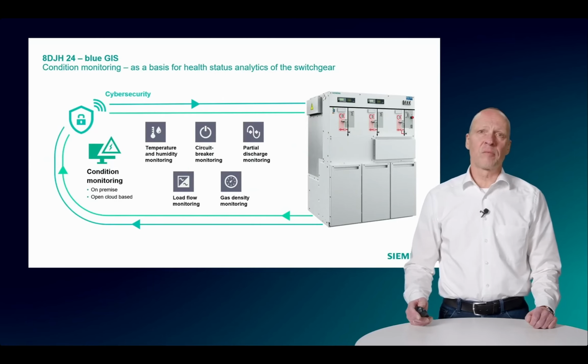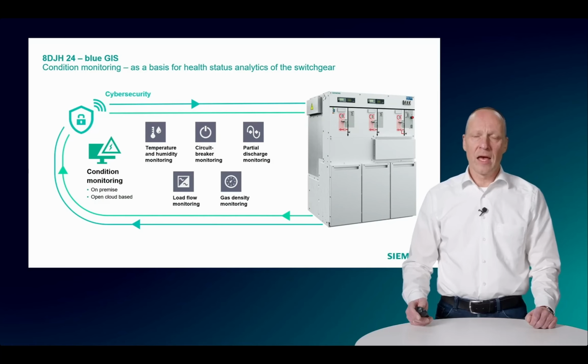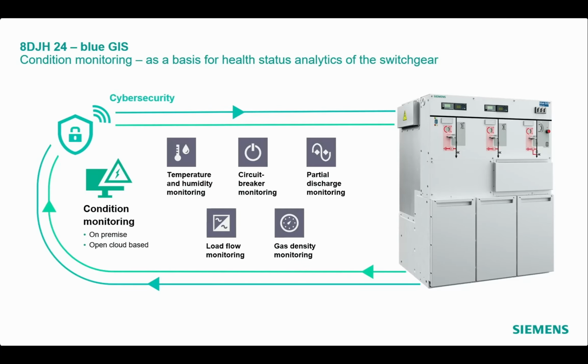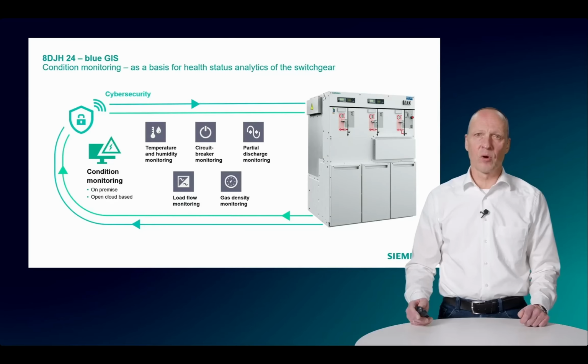The 8DJH24 Blue GIS, as well as all our other GIS switchgear, can optionally provide a condition monitoring to predict the health status of the switchgear, as well as a monitoring of grid operational data. Temperature and humidity monitoring can detect abnormal operating and ambient conditions. The circuit breaker can be monitored to prevent switching failures. Electrical insulation can become damaged over time due to faulty or incorrectly installed peripheral components. As a consequence, partial discharge may occur. Our partial discharge monitoring system provides an early warning to avoid failures and damages on the switchgear. Gas density monitoring reports a warning in the very rare event of a gas loss.